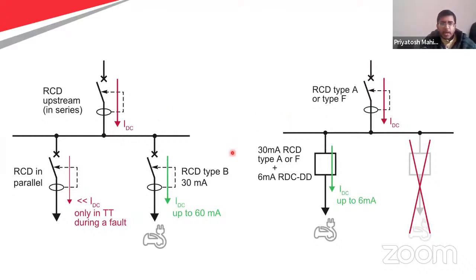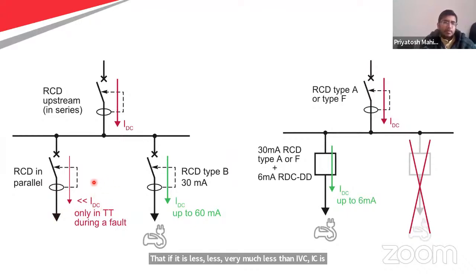So that is the way. Now you see here, if you connect this RCD type A or F - actually I just missed one point - if you connect type B, then on this side, if it is very much less than IDC, meaning IDC is up to 60 milliamp. I expect that they are all symmetrical to each other, so it is also allowing 60 milliamp.